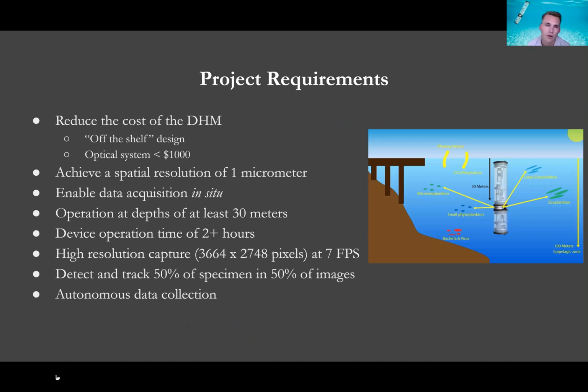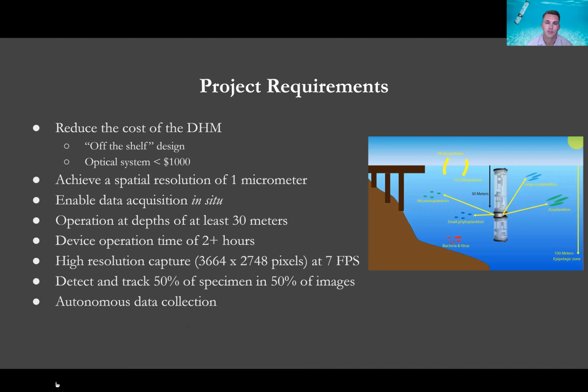So our main goal of this whole project was to reduce the overall cost of the DHM, as Alex mentioned. So we have a design requirement for the optical elements to be less than $1,000. And this includes an onboard camera, which is capable of 1 micron spatial resolution. On top of that, the data has to be collected in situ, which means in the ocean environment at a depth of at least 30 meters for an operational time of over 2 hours.